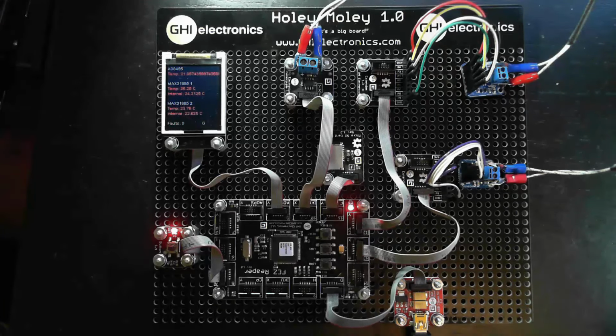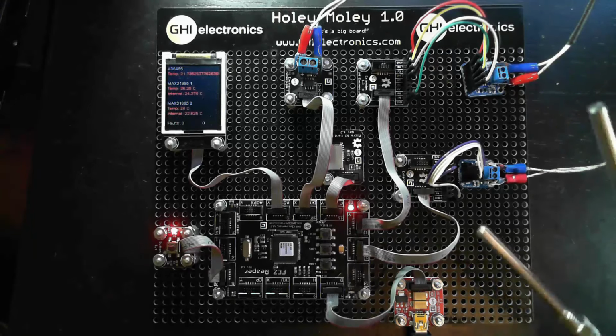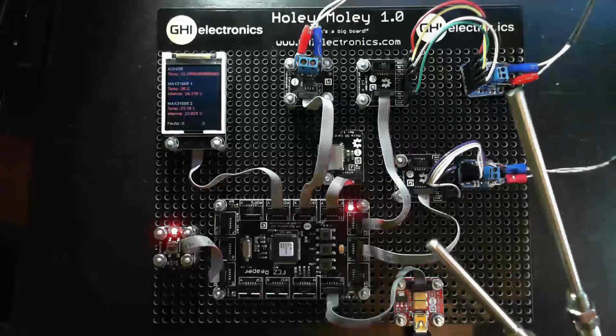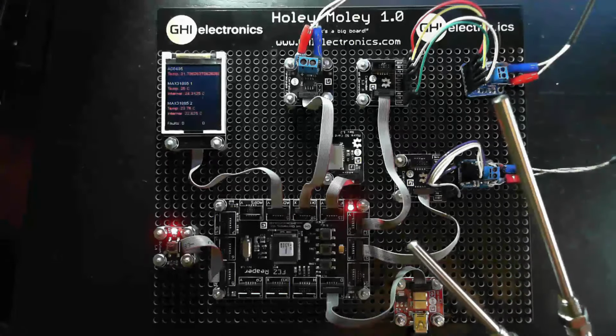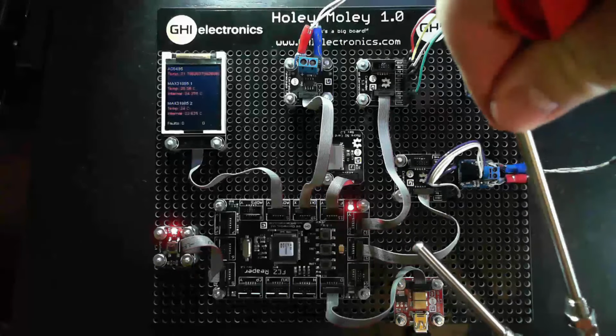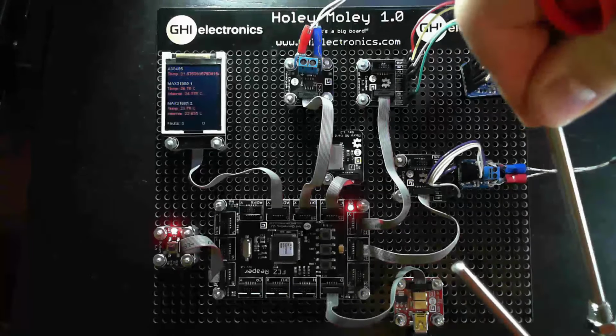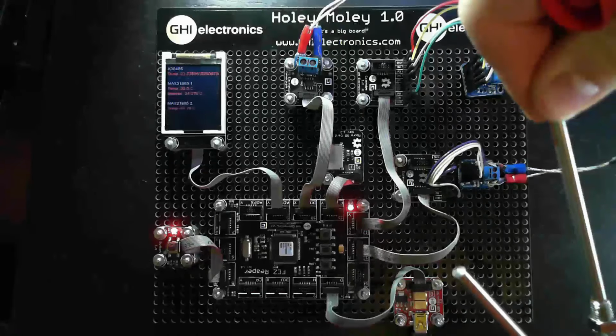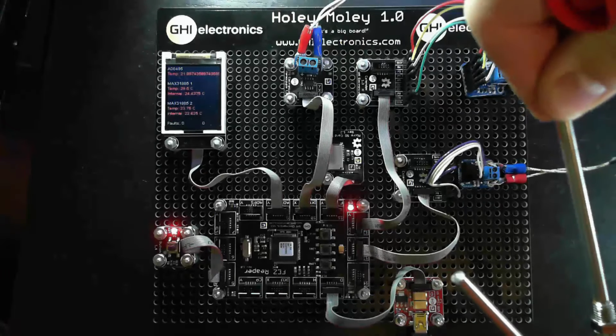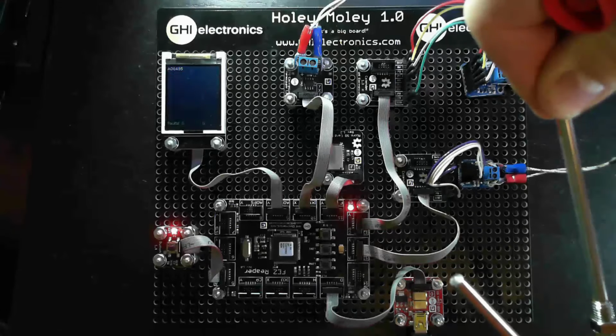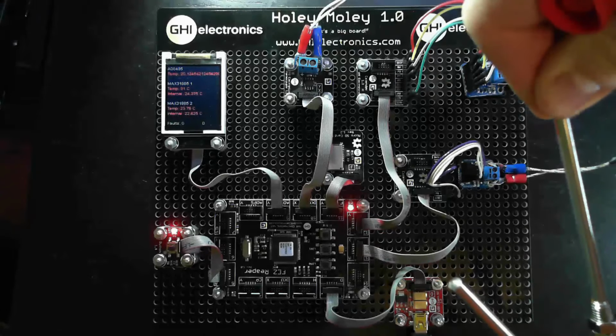One thing I should point out about wiring up these probes: I'm not particularly sure any of the vendors pay attention to color codes or polarity. So when I hook these up, my electric Kool-Aid acid test is to grab one of the probes, because my body temperature hopefully is higher than ambient, so I should see the temperature going up like here, up to 30.31 degrees Celsius.